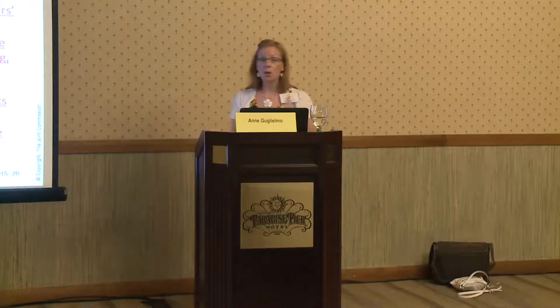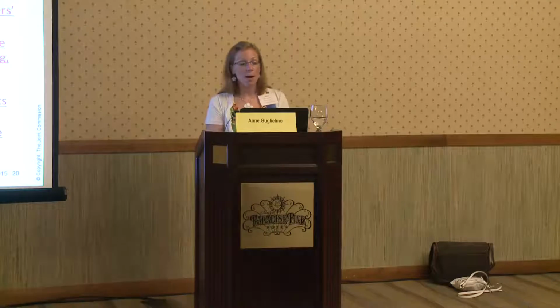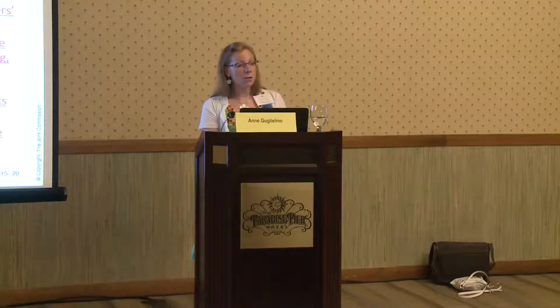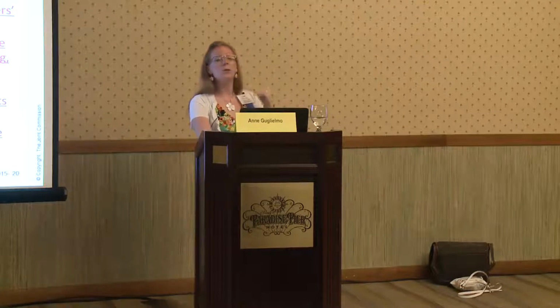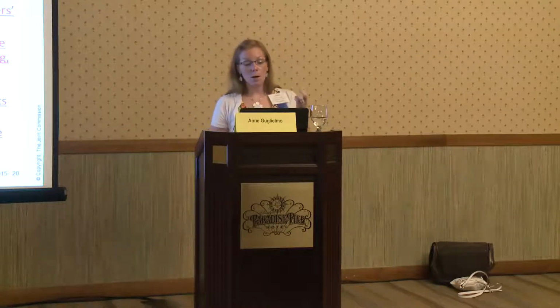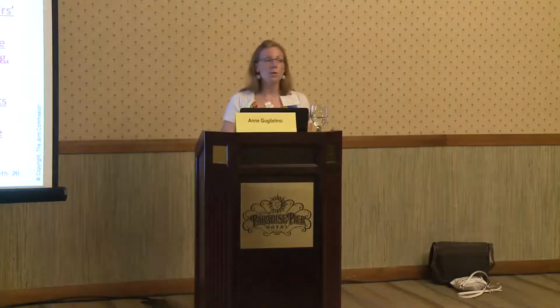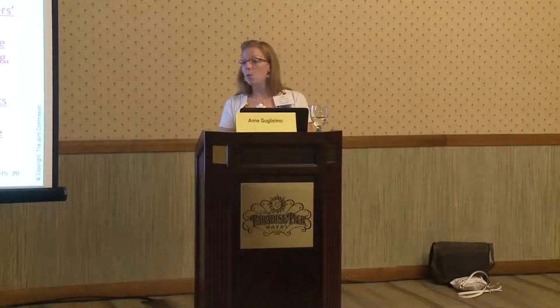Now, there are some pieces of equipment, and this also ties over to medical equipment, that cannot be put on an AEM. If you are going to use an AEM, you have to be very careful about which pieces of equipment you use an AEM on. If the equipment is subject to any federal, state, or Medicare conditions of participation that requires manufacturer's recs, you cannot put it on an AEM. Also, if you have new operating components that don't have sufficient maintenance history, you can't use an AEM on that because, again, what is the foundation and the basis? You need the maintenance history to be able to do that.